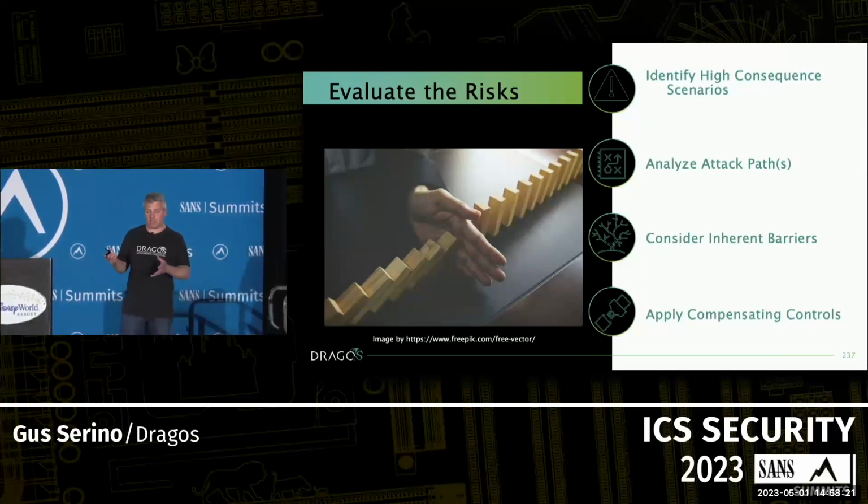I have seen some water utilities whose flow meter is wired directly to their chemical metering pump. So it doesn't matter if somebody changed the PLC program, they're not going to affect the chemicals. And their valves are all manual, so they're not going to isolate anything. Their biggest problem is ransomware, and they have backups. All right, so you don't need to worry about all this stuff. You maybe.